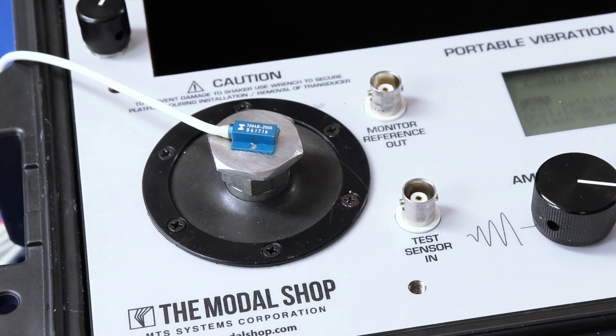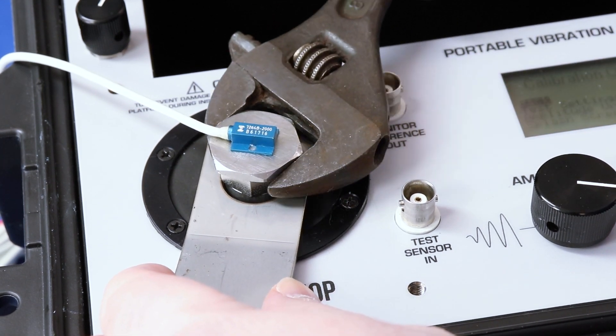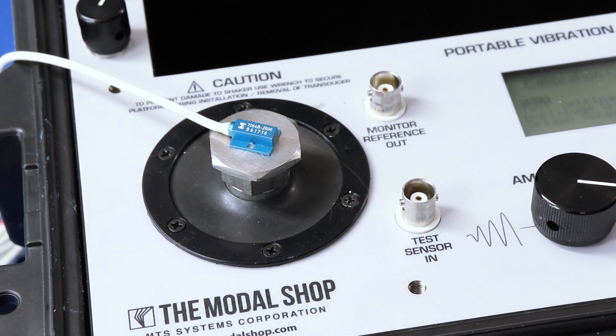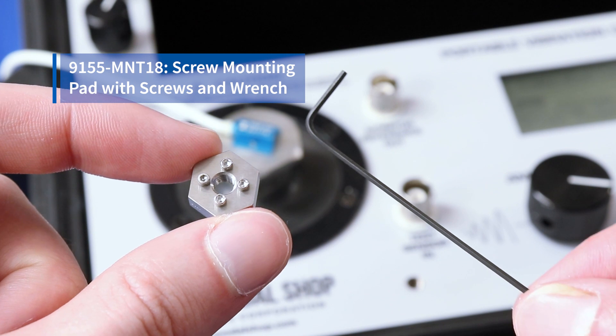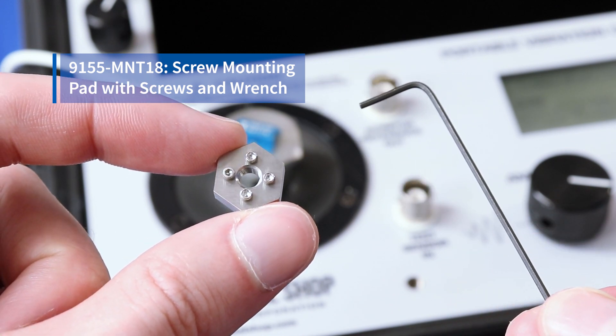Just like that — now it's on there. The next step is to make sure that our mounting pad is nice and tight. About 10 inch pounds of torque; wrist tight is good enough. Make sure you secure the shaker's armature, and tighten with a crescent wrench or a torque wrench against that shaker armature. The 9100PR is supplied with the model 9155-MNT18 screw mounting pad for piezo-resistive sensors with supplied screws.